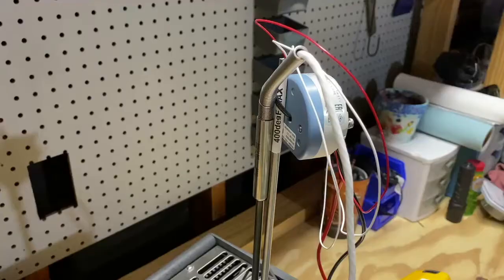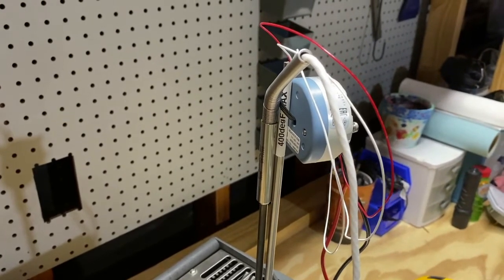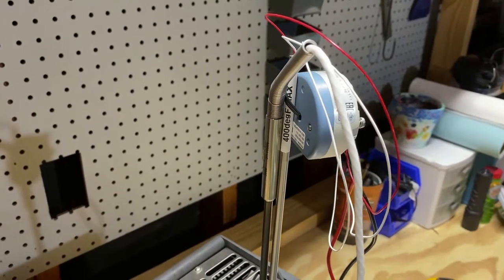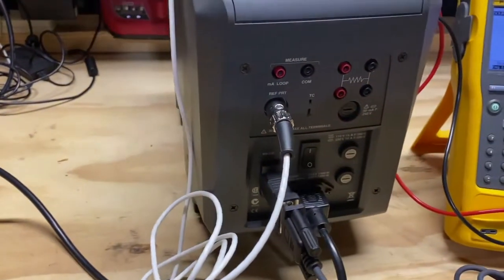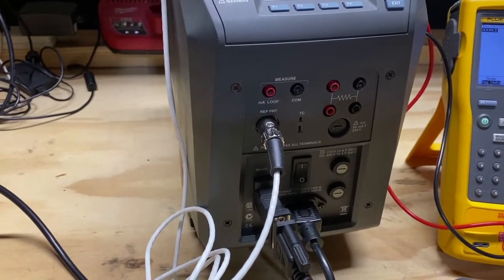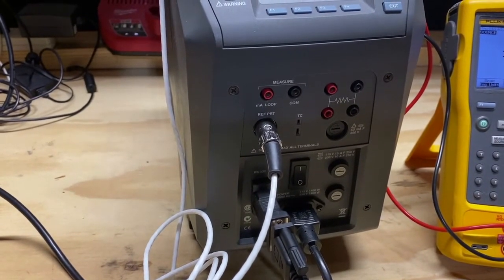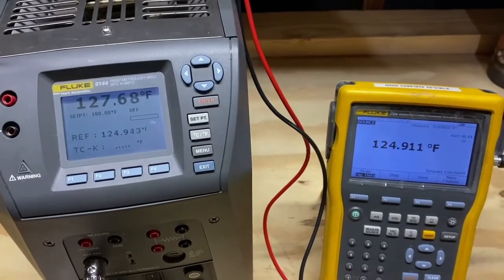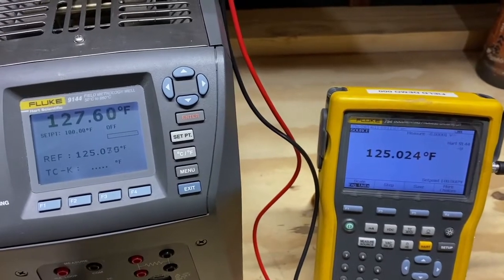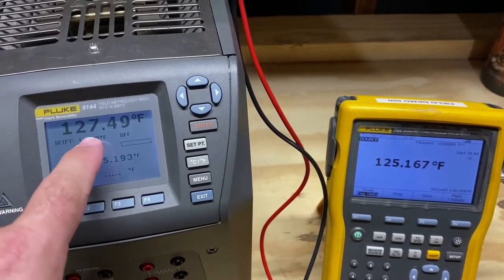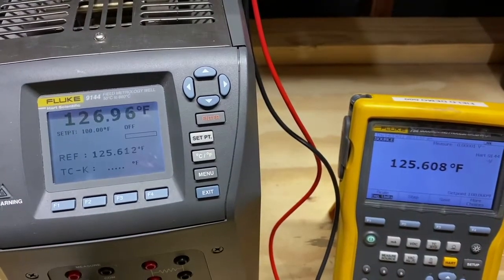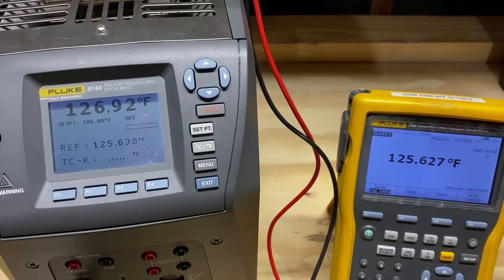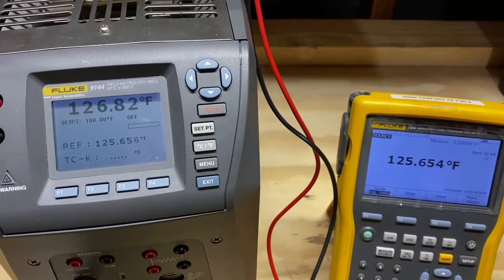To create an even more accurate calibration measurement, we can insert a secondary reference RTD into the dry block. And using the process dry block connections on select dry blocks, plug it directly into the calibrating dry block. This allows the 754 to capture the reference probe measurement, indicated here, rather than the internal block temperature referenced here. This can improve the accuracy of the measurement through the secondary reference, and typically adds an extra digit of resolution.